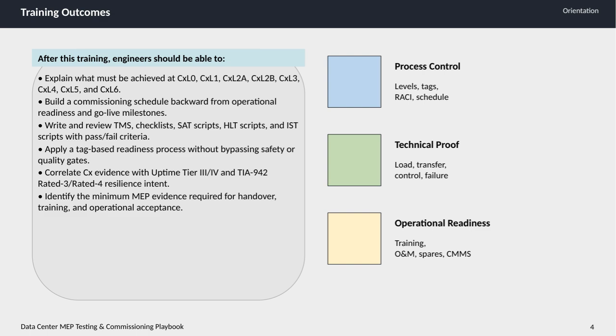It's important to associate the commissioning evidence with industry standards like Uptime Tier 3/4 and TIA-942 Rated 3 or Rated 4, ensuring resilience requirements are met. Additionally, you'll be able to identify the minimum mechanical, electrical, and plumbing evidence needed for successful handover, training, and operational acceptance. The training is structured to cover key process controls, including different levels, tags, roles, responsibilities, and scheduling. Then we move on to the technical proof aspects like load testing, transfer procedures, control mechanisms, and failure handling.